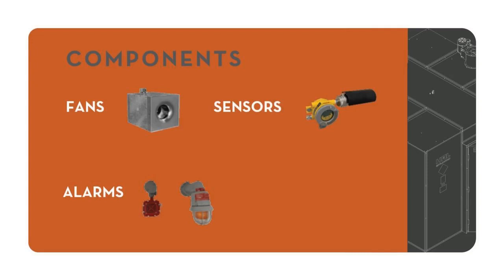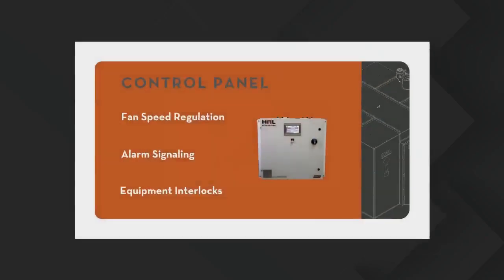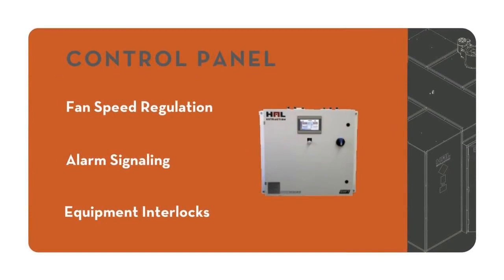The sound alarm and light alarms are there to alert at different concentrations of gas in that room. So the light alarm will alert you when there's 10% of that lower explosive limit, also known as the LEL. And then that sound alarm and light alarm will go off simultaneously with 25% of the lower explosive limit for your given solvent. So these components are great, but the control panel is really the brains of the system. Everything is run through here, and that's how this whole system communicates.